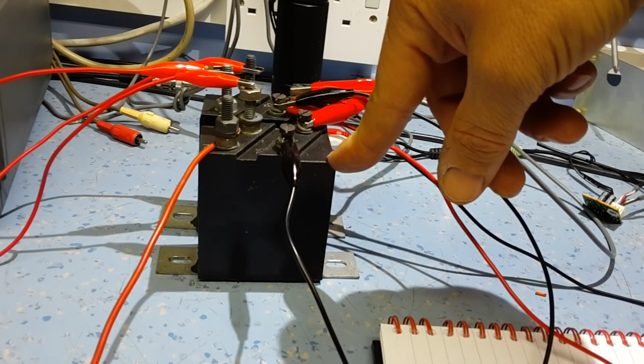For the secondary, I wired the two secondaries in parallel. If I wired them in series, it gave me a lower reading. Wiring them in parallel gave more current capability to overcome the burden, so the extra current gave me the output I wanted. I also tried wiring the primaries in parallel, which gave no extra benefit at all. So the primaries are wired in series and the secondaries are wired in parallel.